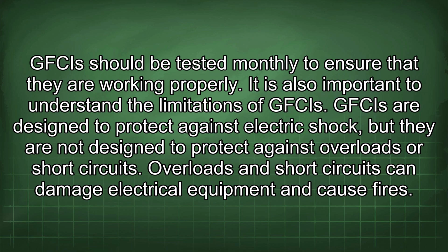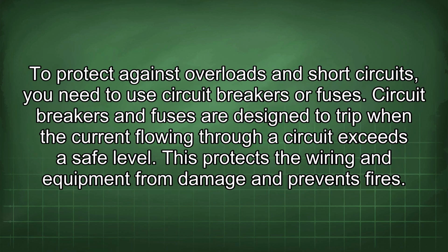It is also important to understand the limitations of GFCIs. GFCIs are designed to protect against electric shock, but they are not designed to protect against overloads or short circuits. Overloads and short circuits can damage electrical equipment and cause fires. To protect against overloads and short circuits, you need to use circuit breakers or fuses. Circuit breakers and fuses are designed to trip when the current flowing through a circuit exceeds a safe level. This protects the wiring and equipment from damage and prevents fires.